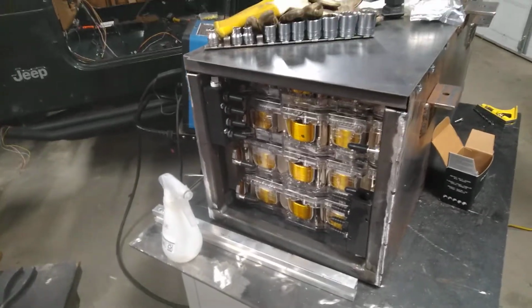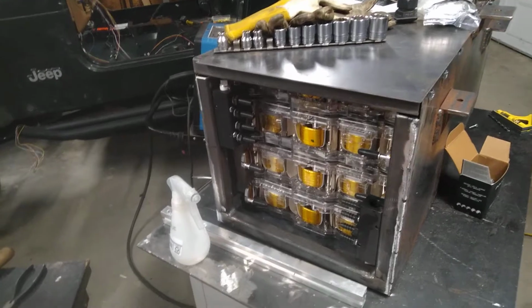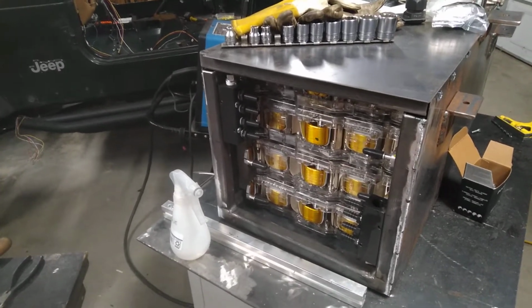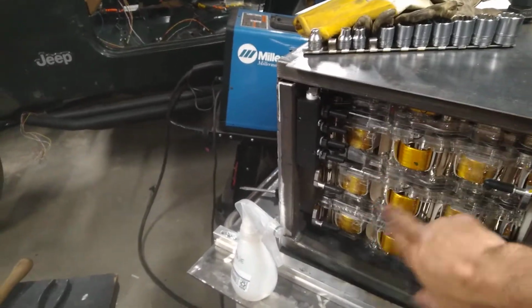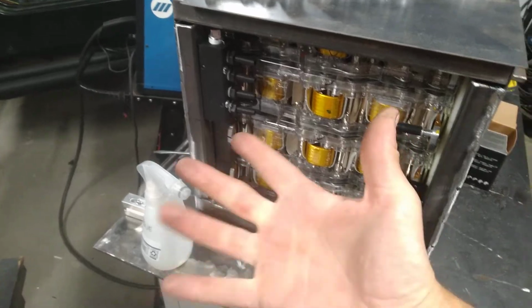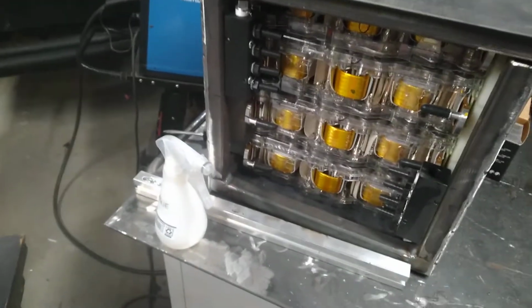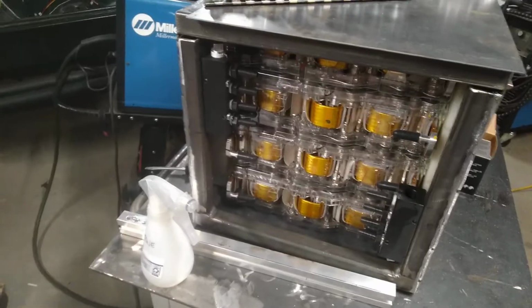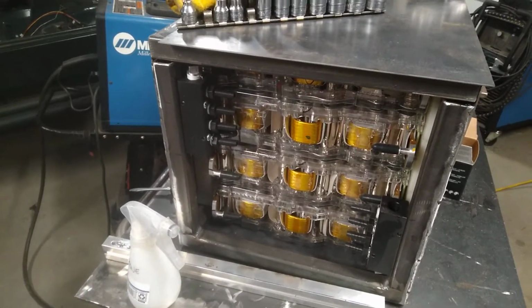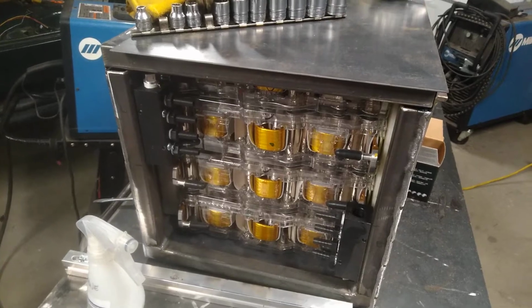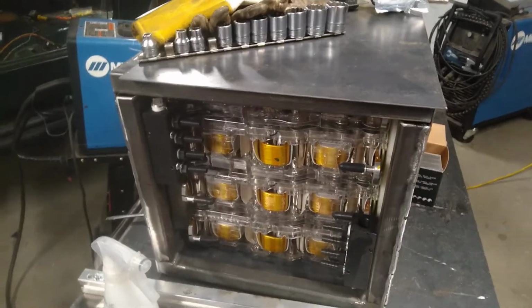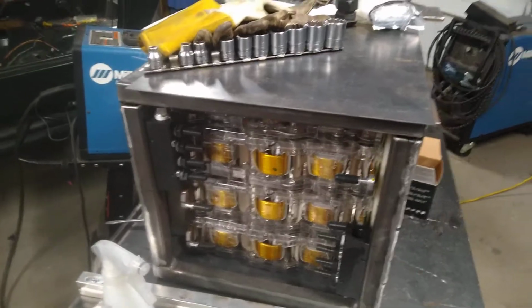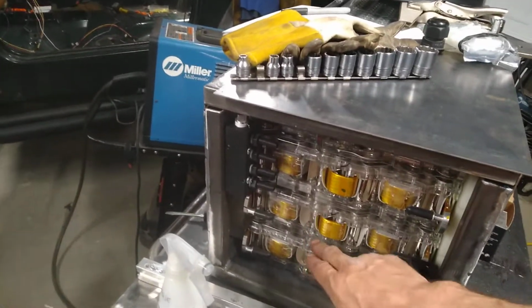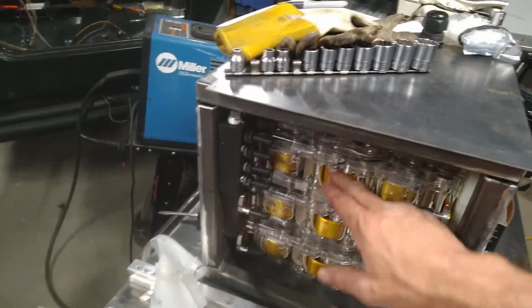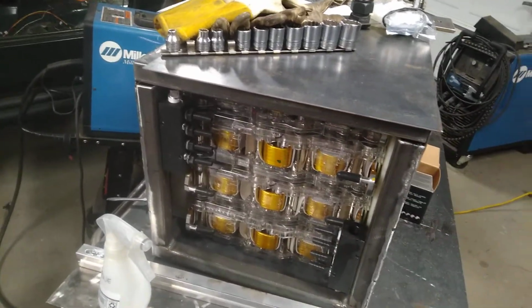What I've come up with is I'm going to use 35-pin Ampseal connectors. Each of these 4 modules has six cells wired in series, so there's going to be 6 outputs for the BMS per module — 6 times 4 is 24. And then there's one thermistor per module also, so 24 and 4 is 28.